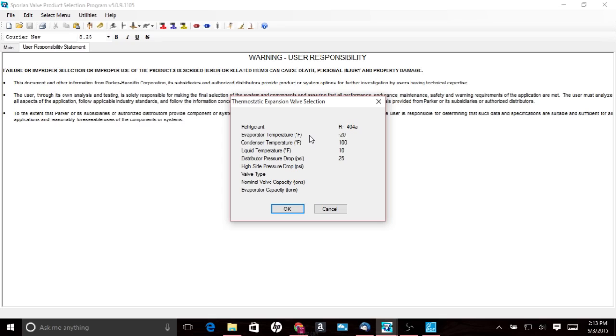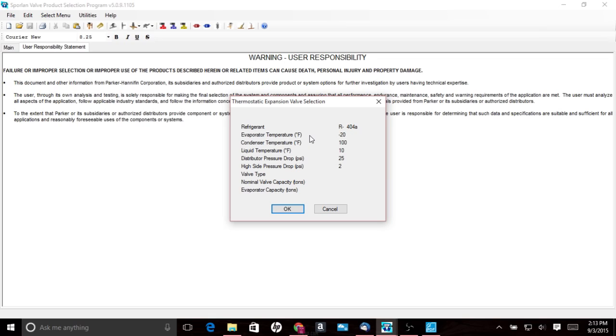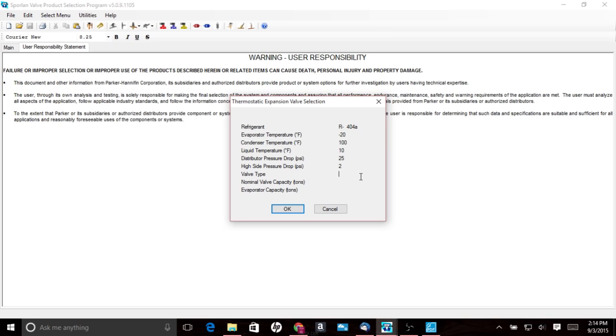So they already have that information and they've already sized it accordingly. So assuming that you go back in with the same equipment, everything, basically all things being the same, you know, they're going to have the right TXV for that. But assuming you didn't have any of that information and you were trying to size an expansion valve, this is where, or you couldn't get the information that you needed. This is where it would go. High side pressure drop. It's not going to make too much of a difference, but you know, you want to have that as low as possible anyway. So maybe a couple of PSI for high side pressure drop valve type. You do have the one thing, one limitation on the selection software is you do have to tell it what valve body you want to have it spit out to you. I would like to see a version of this where it gave you multiple options, but that's just not the case right now.